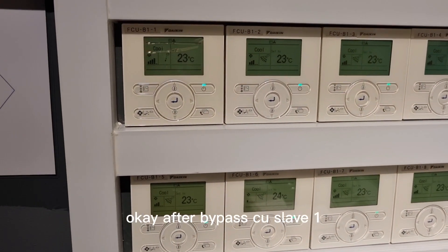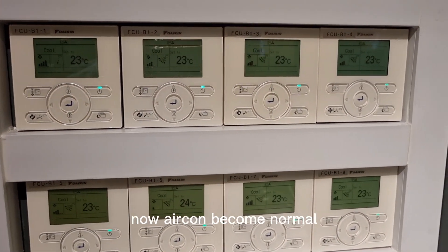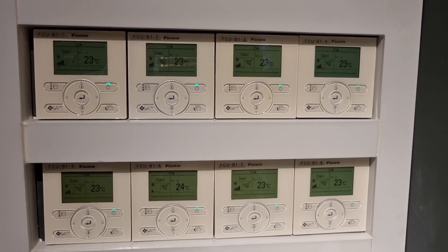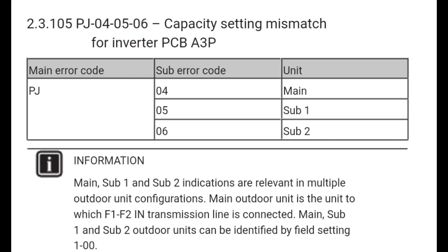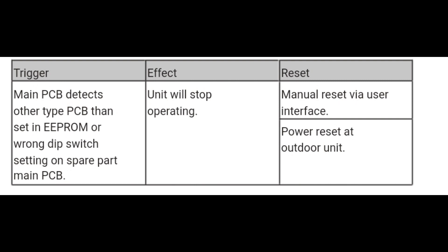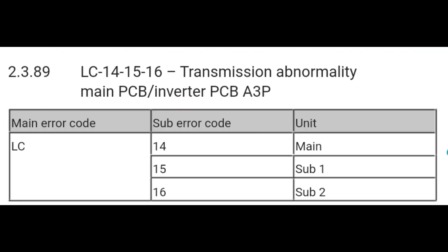After bypassing slave 1, the aircon becomes normal. The slave 1's PCB is faulty.